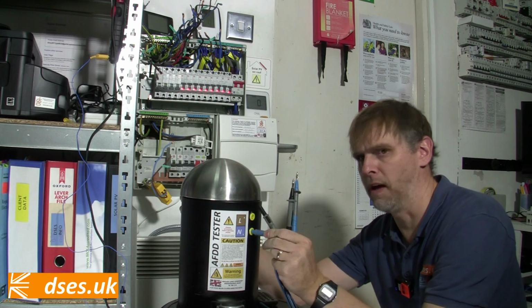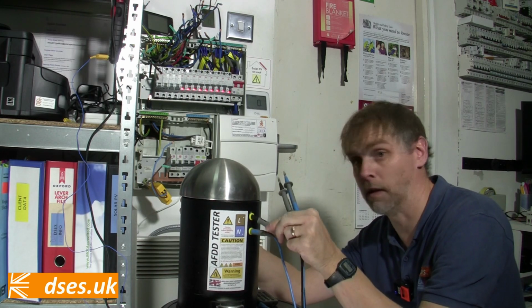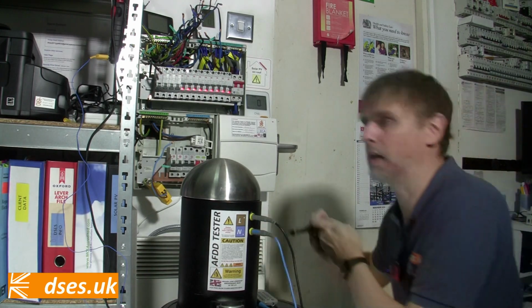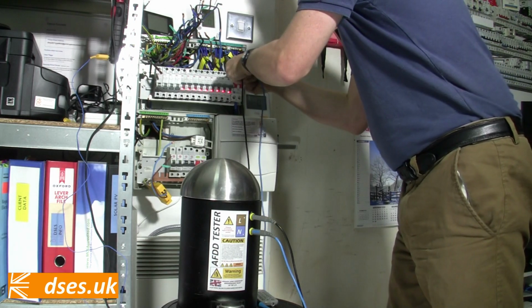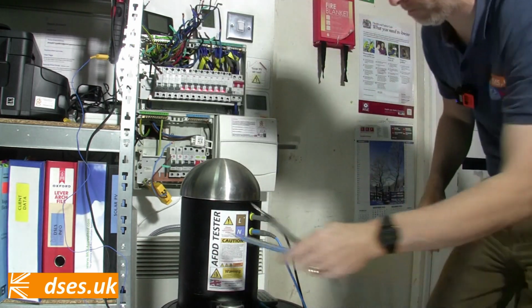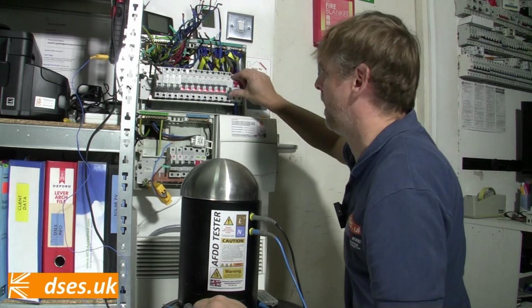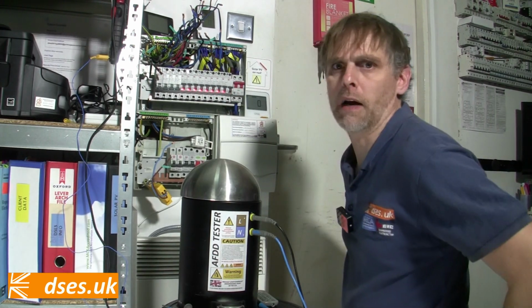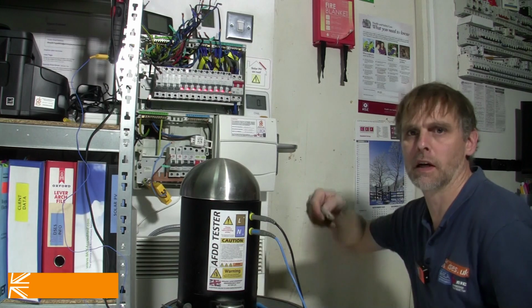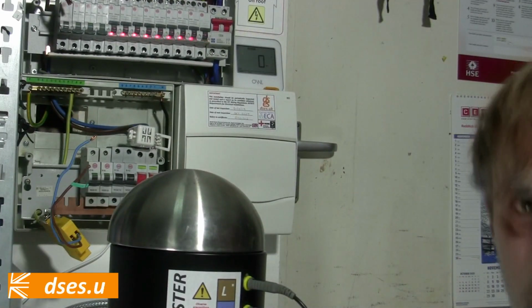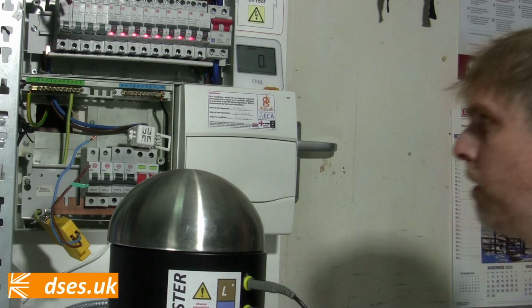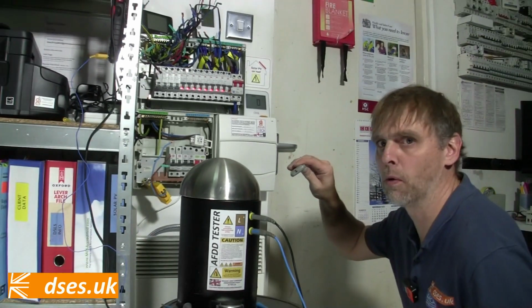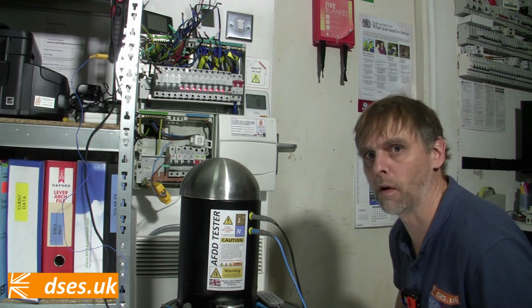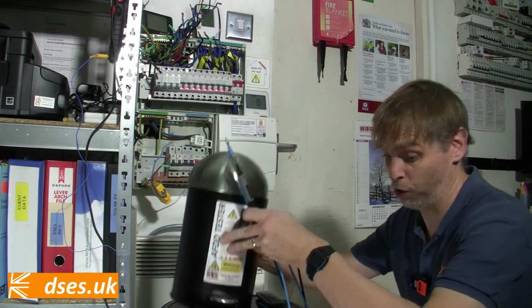Okay, let's use my super AFDD test instrument that I built in the last video to test one of these out. See if it does the biz. Sure enough, it trips off, and when I switch it back on, we have a flashing yellow light. How well does that come out on camera? Zoom in a bit, can you see that? I can't even tell from the viewfinder if you're seeing that or not, but there's a flashing yellow light there. It's just flashing a single pulse to indicate an arc fault problem, or an arc fault trip.